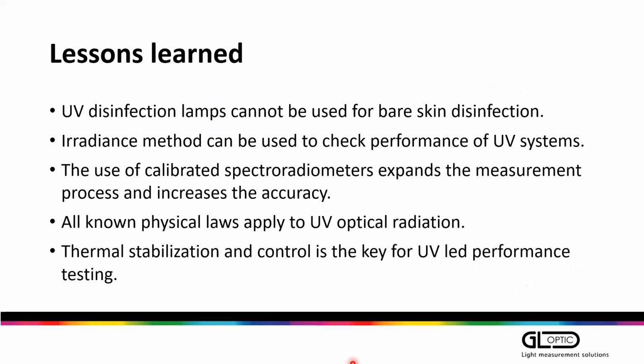Irradiance method seems to be the most straightforward method to evaluate UV systems, especially for disinfection purposes. Our recommendation then on the use of spectroradiometers is connected with the fact that spectroradiometers can detect different wavelengths and can be calibrated for this kind of measurements.